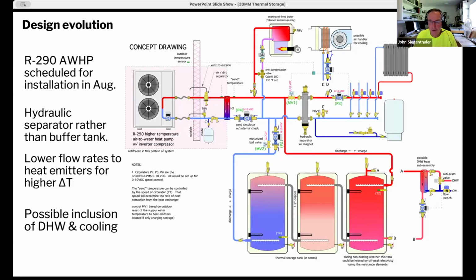The other option is adding domestic hot water. There are multiple ways to do it, but the detail on the lower right, that brazed plate heat exchanger, the circulator, the flow switch, could slide to the left and connect between the two A's and the two B's on that tank. That tank becomes the thermal mass that transfers heat through the stainless steel heat exchanger to the domestic hot water.